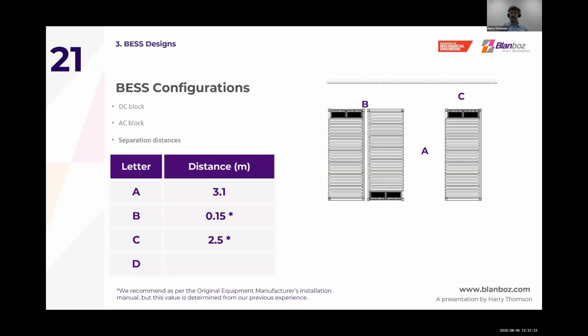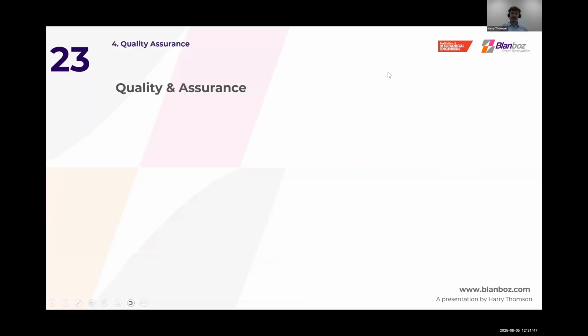And lastly, we have D, which is the distance between the battery container and the MVPS, the medium voltage transformer. We use a value of 5 meters as the basis of a design, but this is really dependent on the type of oil that's used in the MV transformer, as well as the capacity of oil. So again, that's an important factor to check when going through procurement.